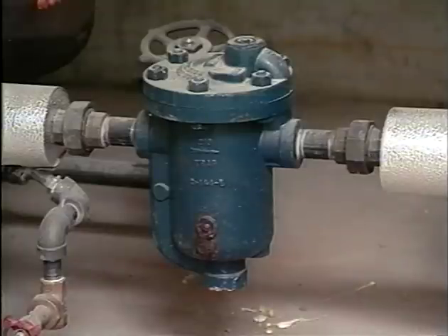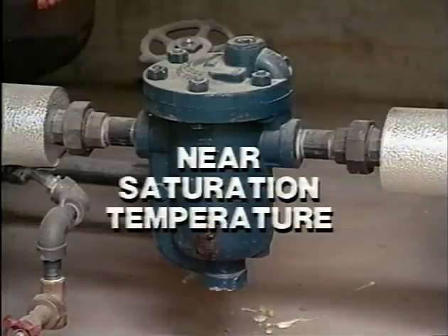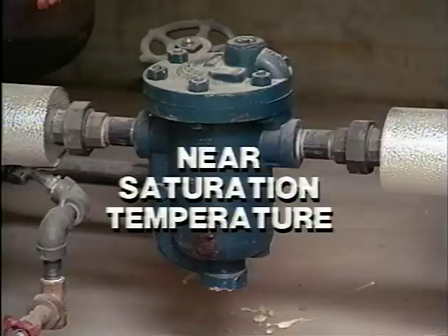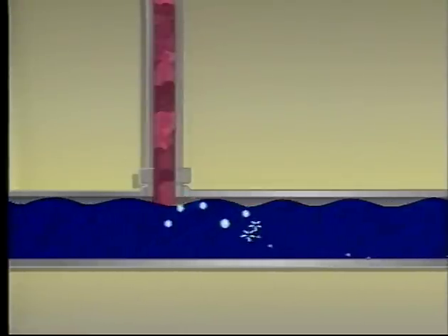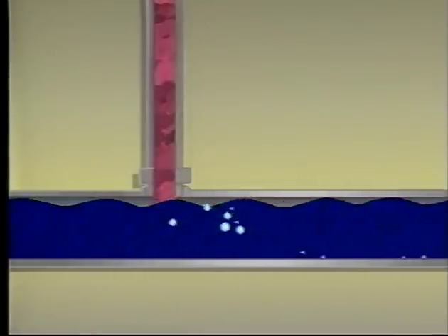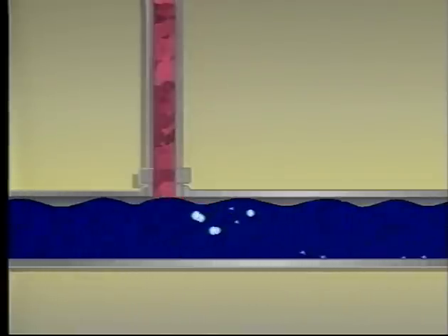The condensate being discharged from the steam trap is at nearly steam temperature when it passes through the trap orifice. When the trap discharge enters the low-pressure condensate line, a great deal of it flashes back into steam.